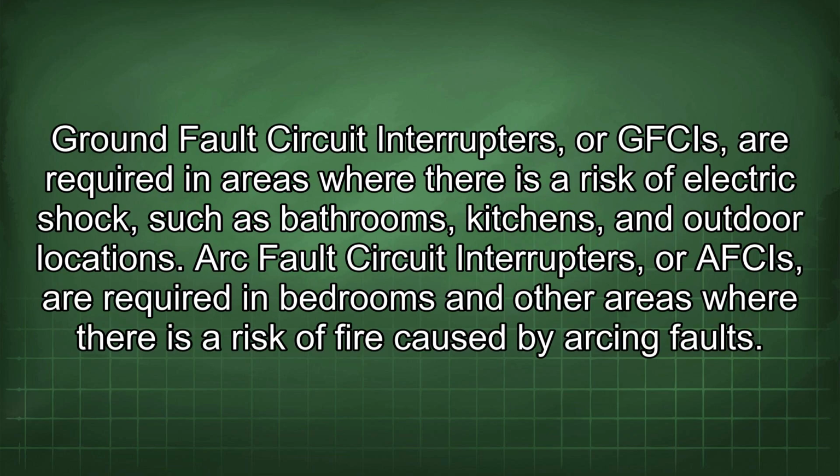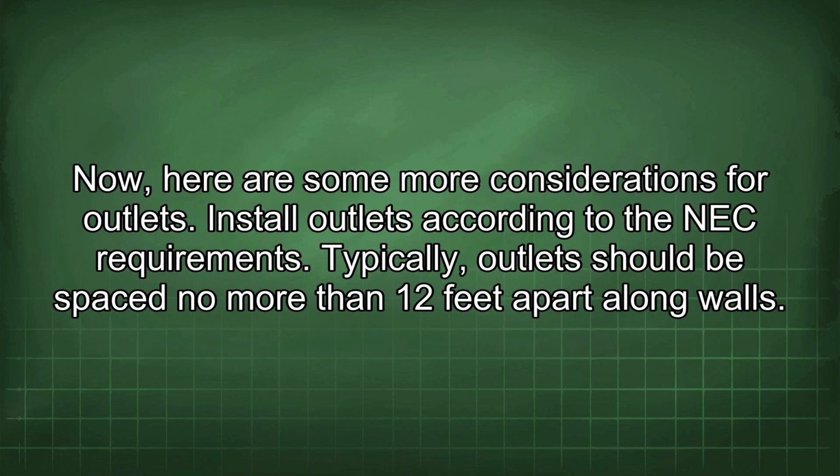Ground fault circuit interrupters, or GFCIs, are required in areas where there is a risk of electric shock, such as bathrooms, kitchens, and outdoor locations. Arc fault circuit interrupters, or AFCIs, are required in bedrooms and other areas where there is a risk of fire caused by arcing faults. Now, here are some more considerations for outlets.